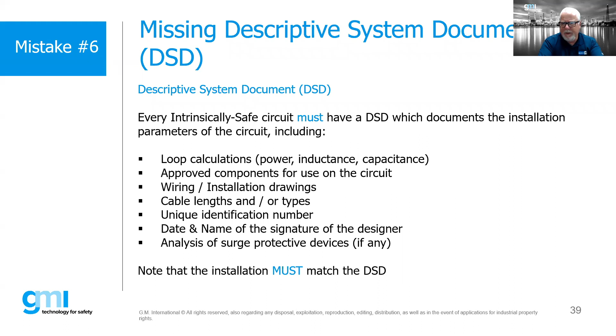So we're talking about the associated apparatus, our field device, any of the cabling, any intermediate devices, as well as the circuit. So we need to have all of that referenced within a single drawing that somebody can go and take a look at and match up to make sure, from both a maintenance and inspection standpoint, that what's actually there matches, and that somebody took the time to make sure that they did all the calculations so that all the safety parameters were met. Those are our entity parameters.